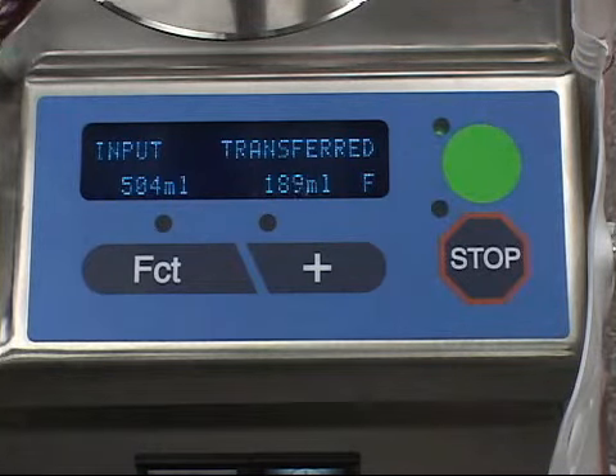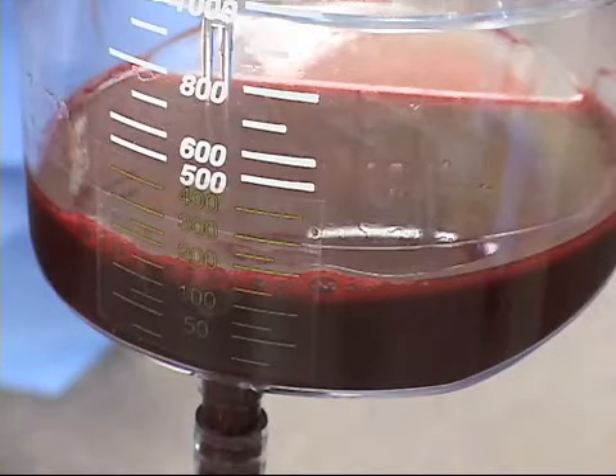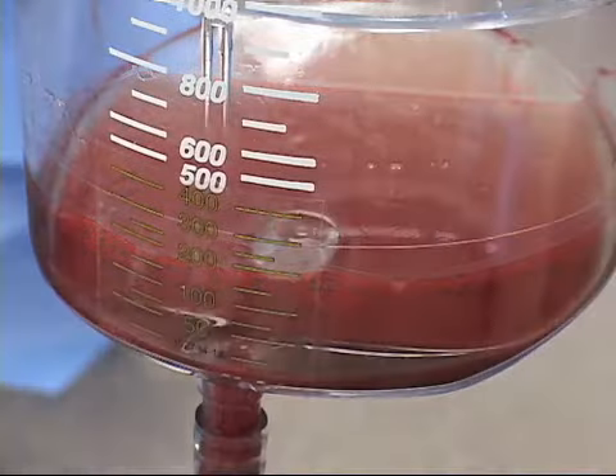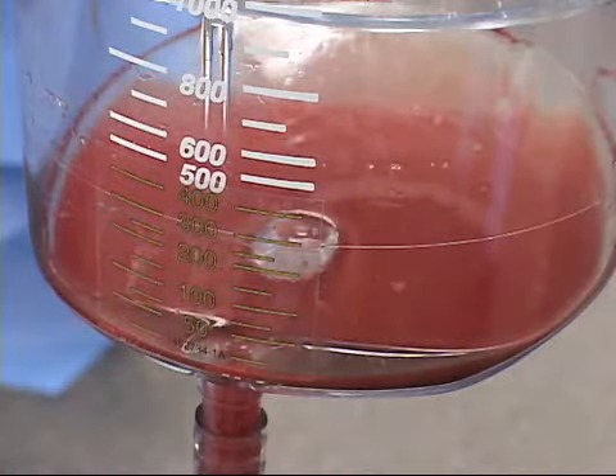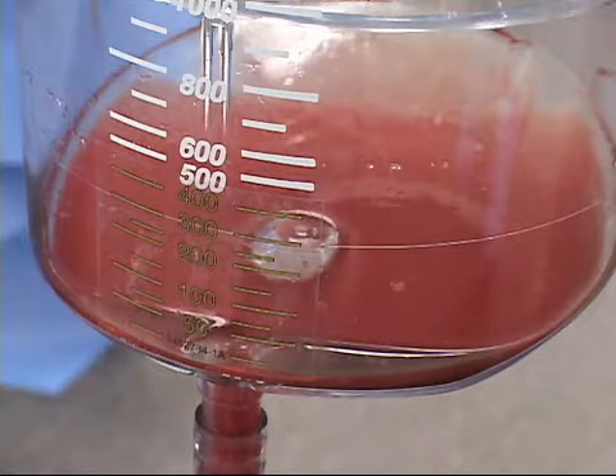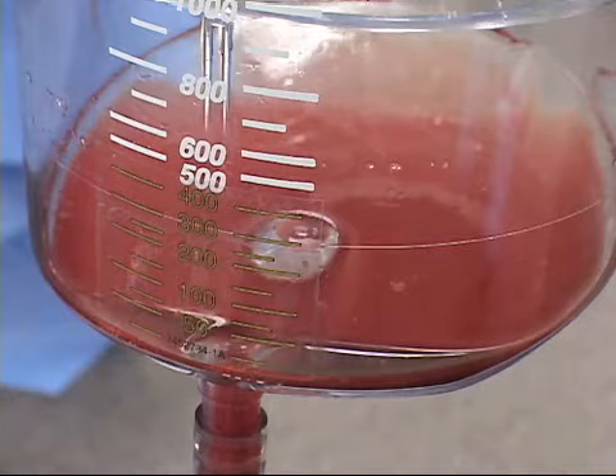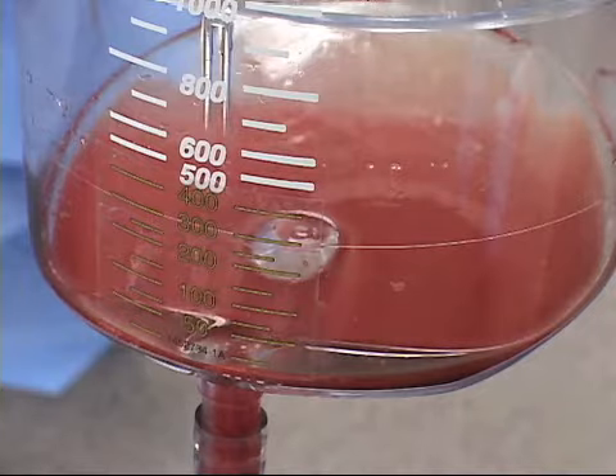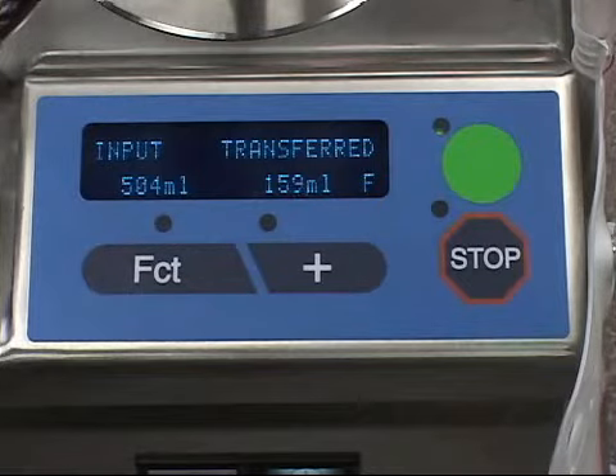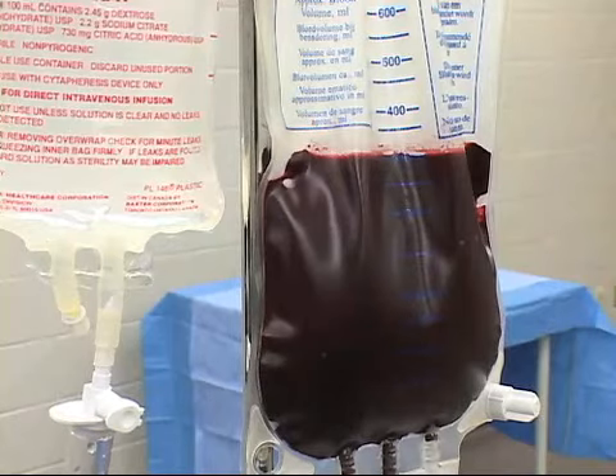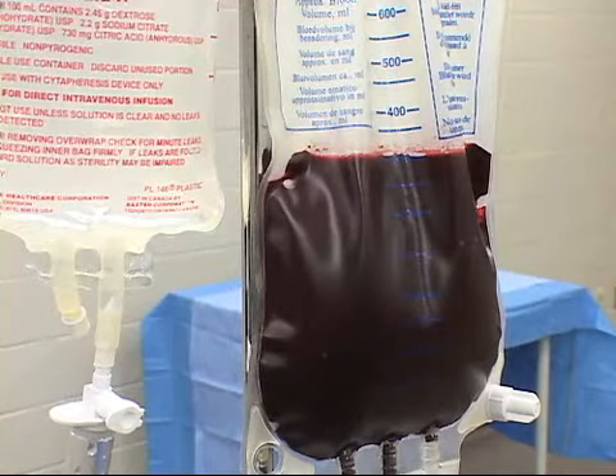In the post cycle, the total volume transferred is displayed. If there is still liquid volume in the collection reservoir, another wash cycle will start automatically. If there is no liquid volume remaining in the collection reservoir, the machine will go into standby and wait for you to initiate another wash cycle by pressing the Go key, or when another 800 milliliters of volume in the collection reservoir is detected. When the wash cycle is complete, the red blood cells are automatically transferred to the 1,000 milliliter holding bag for later reinfusion to the patient.